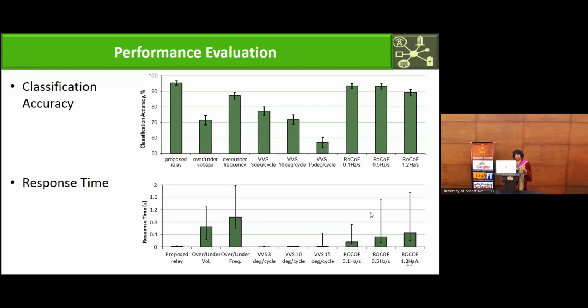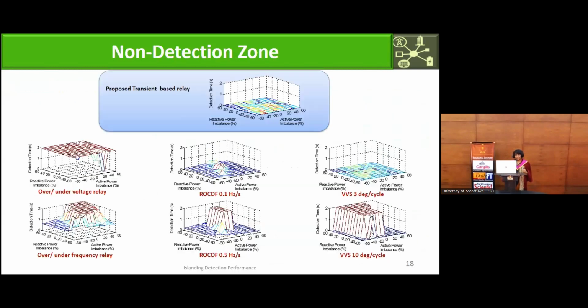So it is very important for microgrid to change its control, so such performance is very acceptable. Another good observation of my proposed relay is that this non-detection zone was 0. Non-detection zone means the relay cannot detect it, because usually the microgrids are designed to be self-sufficient. So at the time of disconnection from the grid, the power imbalance is near 0, so these other passive techniques can fail to detect at that time. We call it non-detection zone, and the proposed method is not depending on the power imbalance.